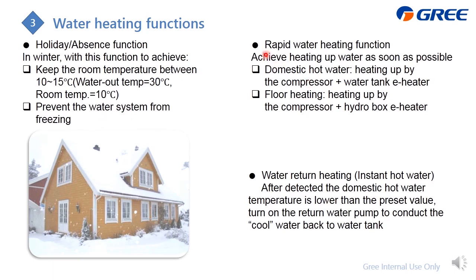And the next is the rapid water heating function. That means you need to get either the domestic hot water or the floor heating as soon as possible. At that time, we can activate the compressor and also the e-heater. For DHW it is the water tank. For the floor coil, it is in the hydro box. So with these two together, we can get the hot water as soon as possible.